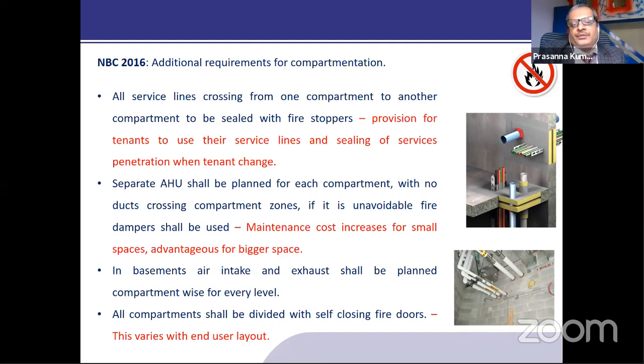And also the AHUs: the code specification is that we should have AHUs compartment-wise, and it is better to avoid ducts moving from one compartment to another. If it is an unavoidable situation, we have to use dampers. Once again, the cramping in the market is the smaller floor plate, the cost of the AHUs. With the bigger floor plate, yes, it is an advantage because the cost of the ducting, the size of the ducting, everything will come down. In the basement, we use the air intake and exhaust compartment-wise and level-wise.